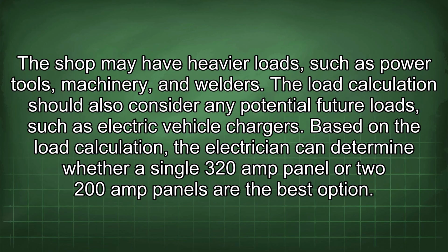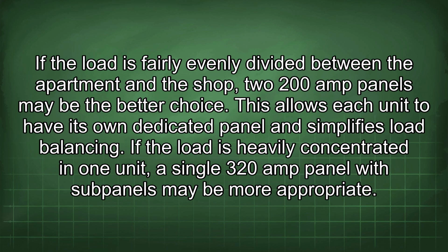Based on the load calculation, the electrician can determine whether a single 320 amp panel or two 200 amp panels are the best option. If the load is fairly evenly divided between the apartment and the shop, two 200 amp panels may be the better choice. This allows each unit to have its own dedicated panel and simplifies load balancing.